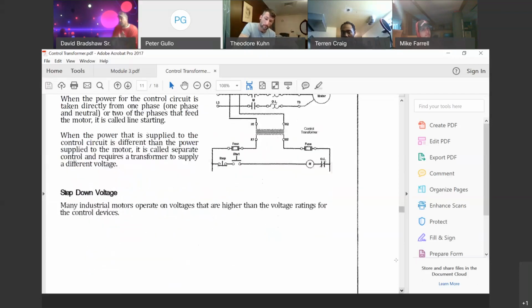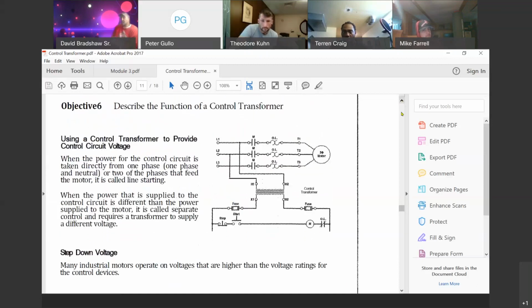Just to add one thing about that schematic, and to reiterate, Dave, this is one of the advantages of three-phase power, guys: you can tap off and get 120. They're using a transformer in this case, so there's no neutral. Remember what Dave mentioned way back: when you have L1, L2, and L3, there's no neutral shown. So when you tap off two hot wires with a DMM, you get the 208. What's great about this transformer is that it's a step down. We're taking the 208 and stepping it down to 120 on the secondary. So you can use a three-phase motor, and you can also use the 120 for a single-phase load. The secondary is basically the 120.